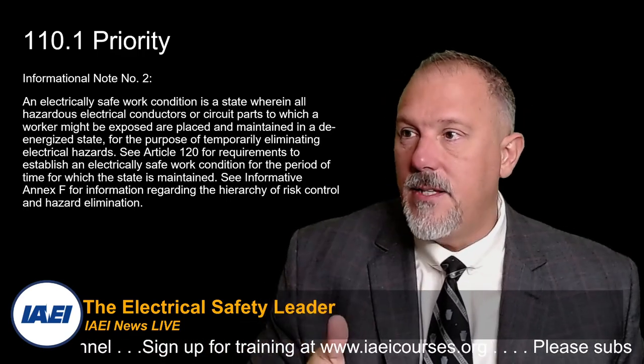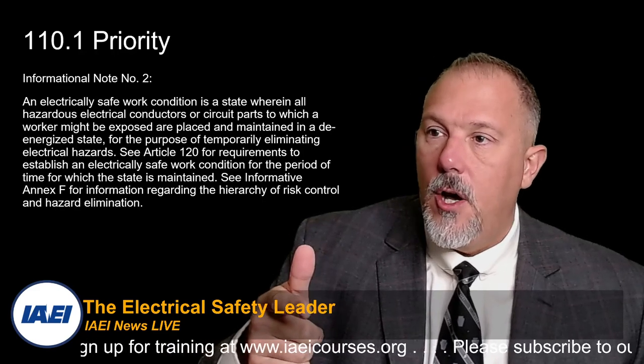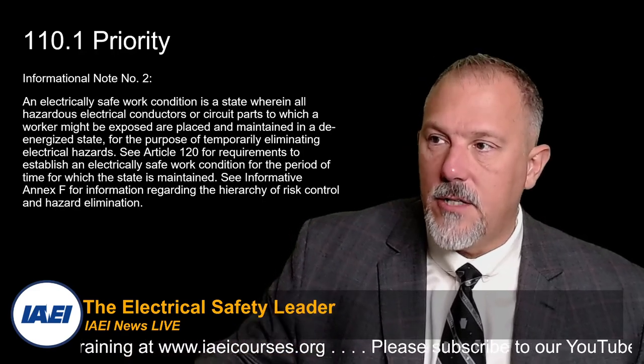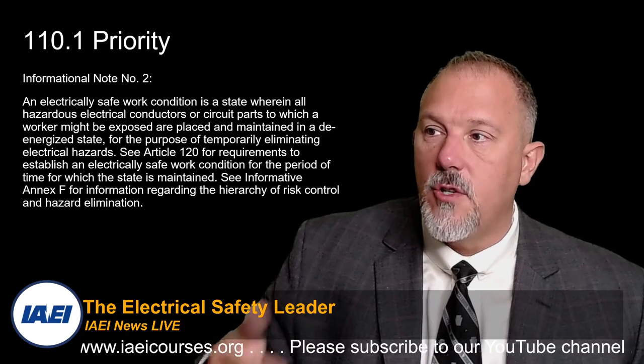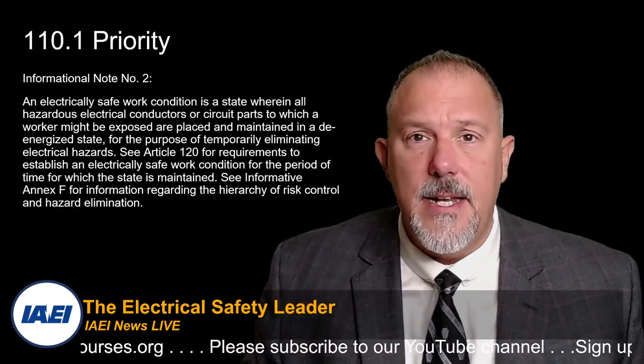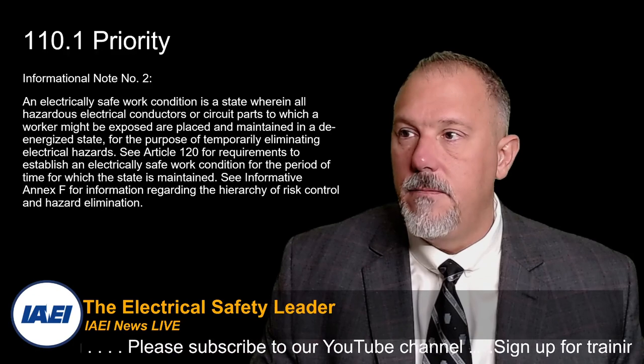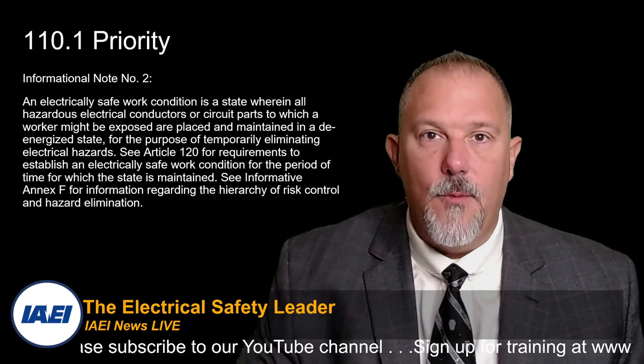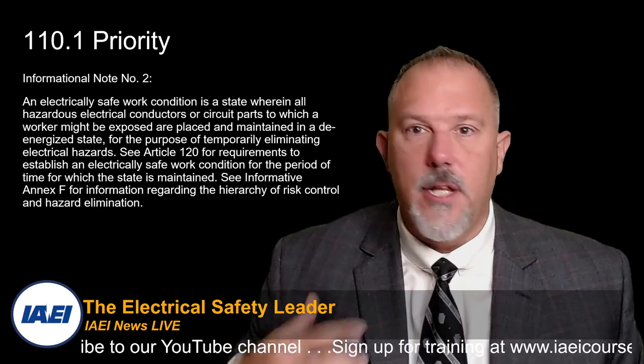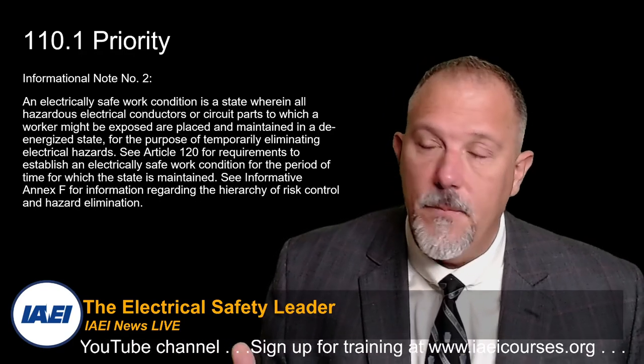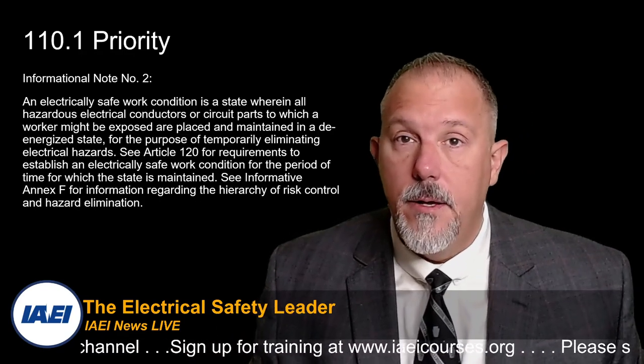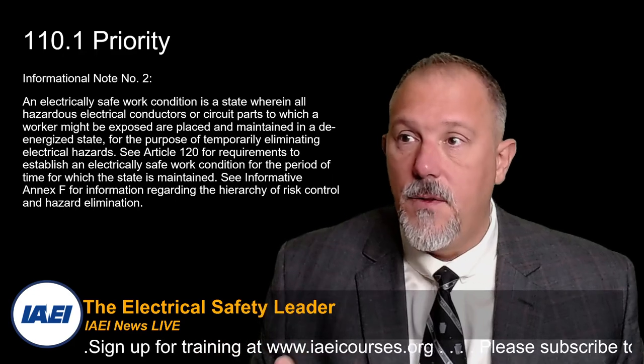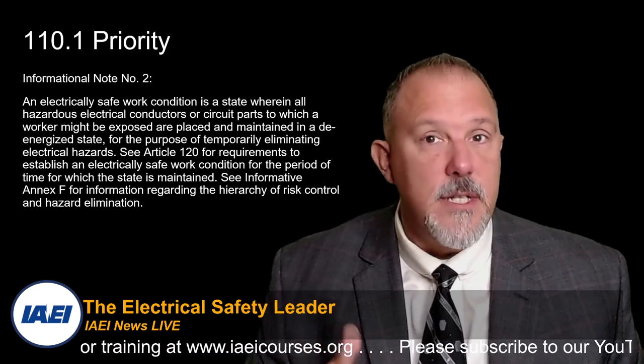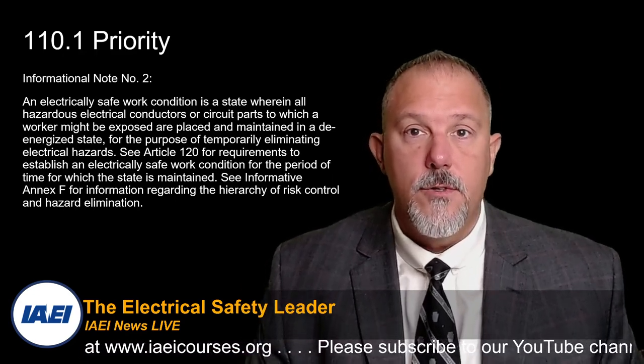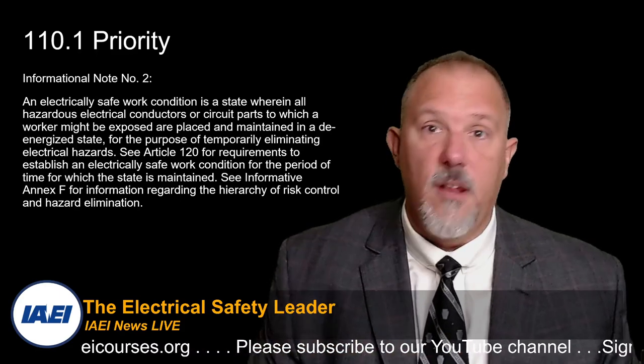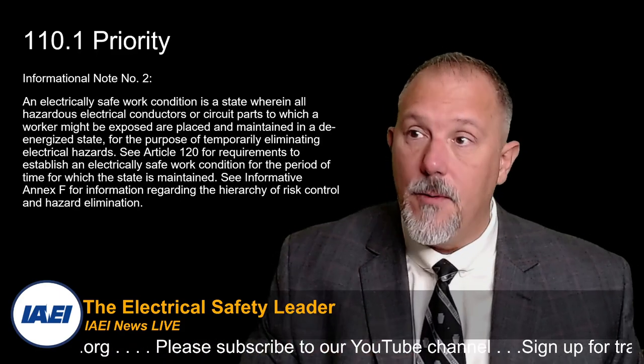I mean, all hazardous electrical conductors or circuit parts to which a worker might be exposed are placed and maintained in a de-energized state. If I don't understand what the qualities of a hazardous electrical conductor are, then I can't achieve 110.1 priority. I can't establish an electrically safe work condition. So you know, we're going to have a discussion about the qualified person at some point in our hour together.